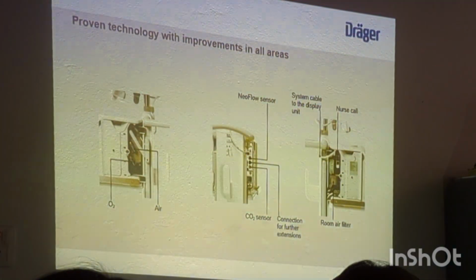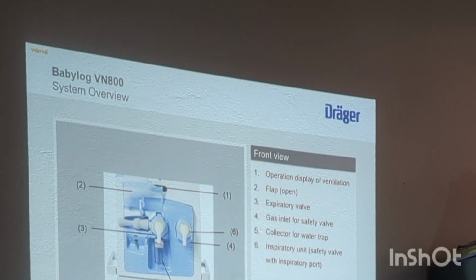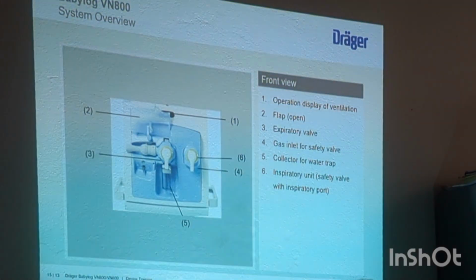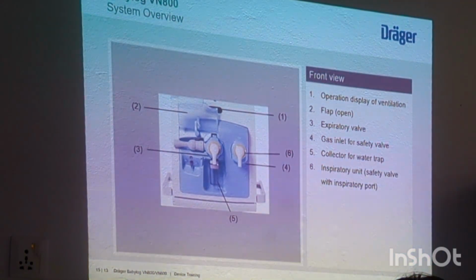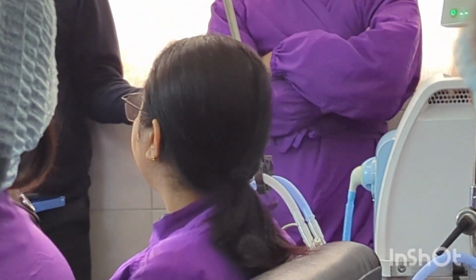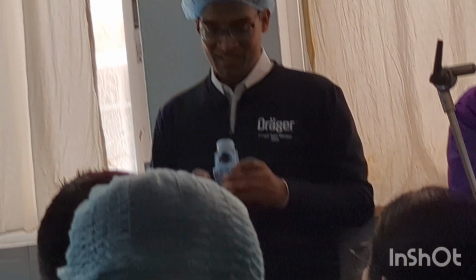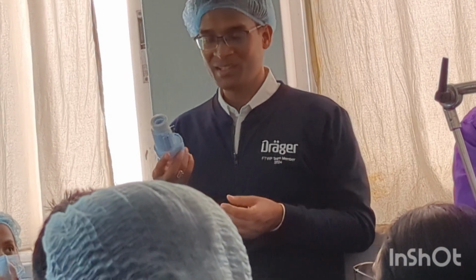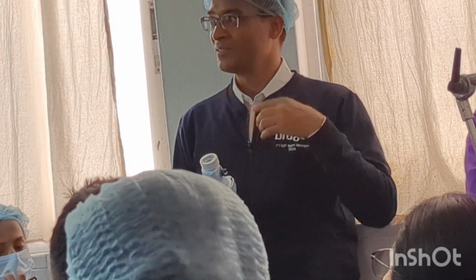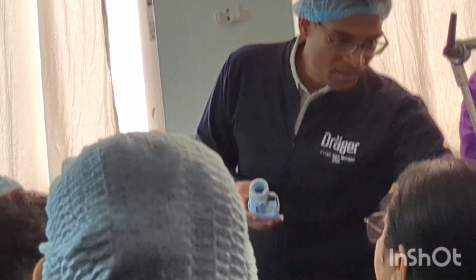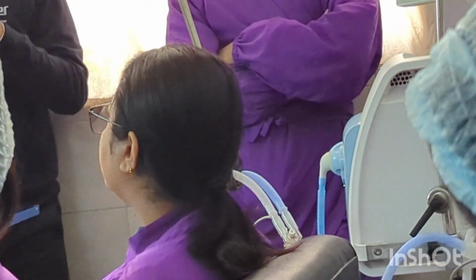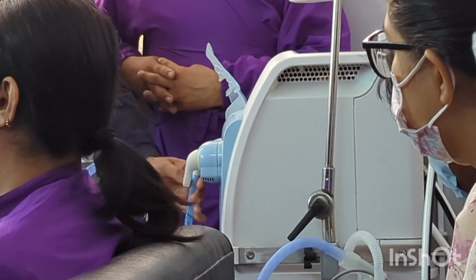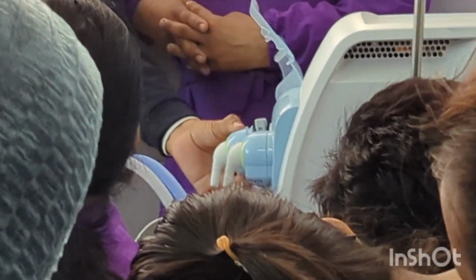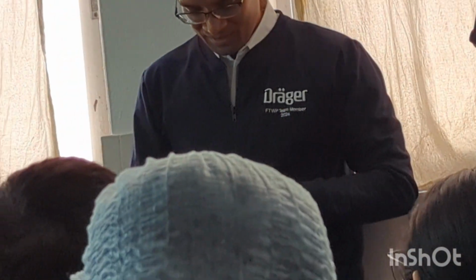So we all know the incidents with devices, so this inspiratory safety valve can also be dismantled from the device by the user. Till now there is no complaint, but if your expiration valve also fails, it's one more safety mechanism. There are two valves. The patient can also expire through this inspiratory valve, so it not only acts as an inspiratory valve. Even if something gets blocked in the expiratory circuit, the patient can inhale and exhale through it. This is also very simple, with lock and unlock symbols, so you can remove it and take it out.